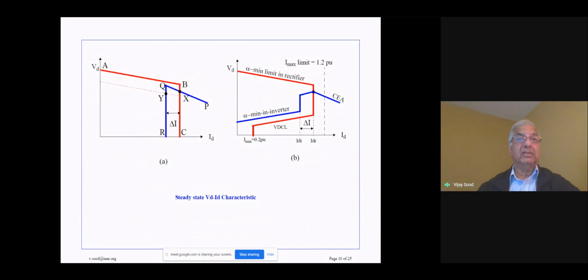And wherever these two characteristics intersect, that will be the operating point for the DC transmission system. So for instance, this point X defines the operating point for the two converters. The rectifier is operating on the constant current characteristic. The inverter is operating on its constant voltage characteristic, or the constant extinction angle characteristic. And this point X now defines the operating point for the transmission system.